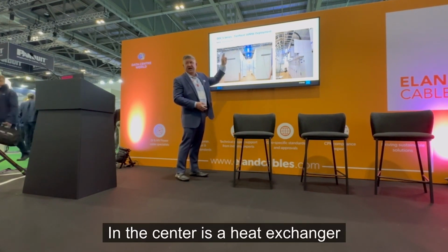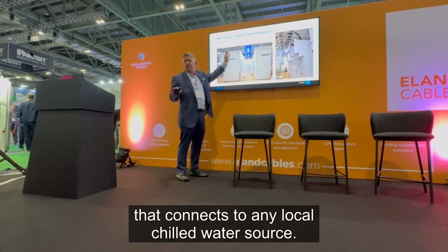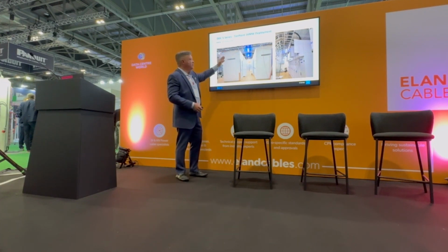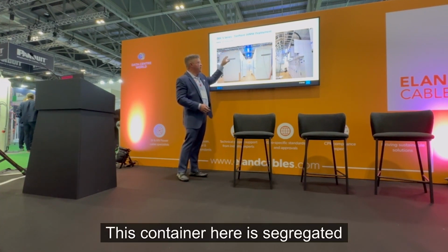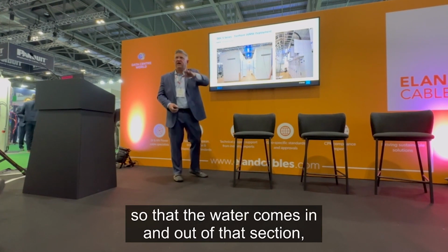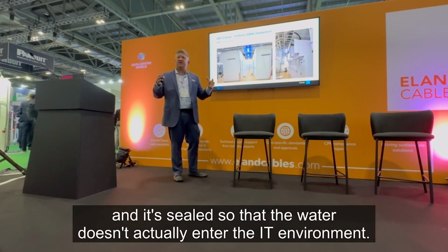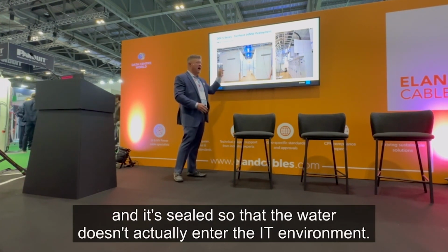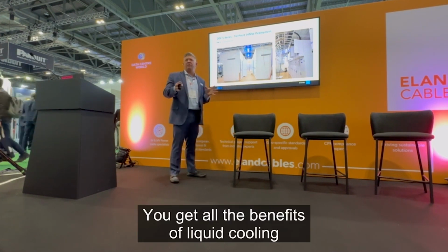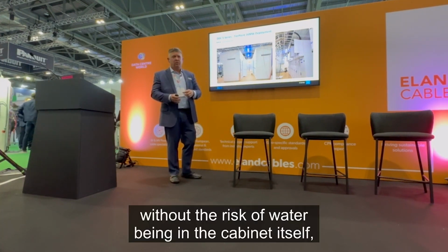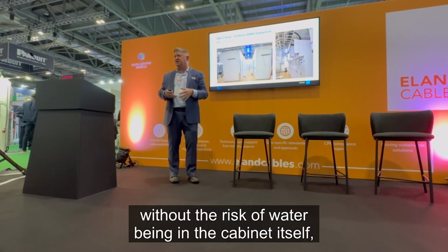In the center is a heat exchanger that connects to any local chilled water source. This container here is segregated so that the water comes in and out of that section, and it's sealed so that the water doesn't actually enter the IT environment. So you get all the benefits of liquid cooling without the risk of water being in the cabinet itself.